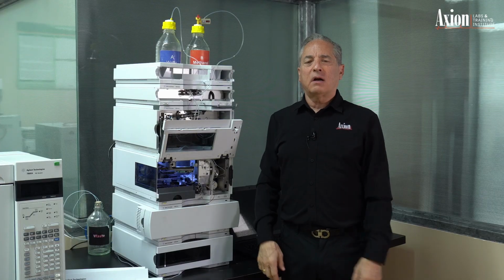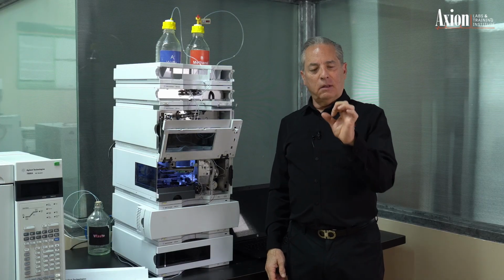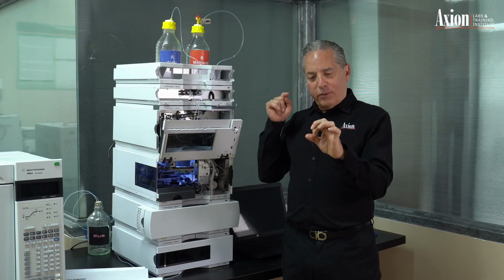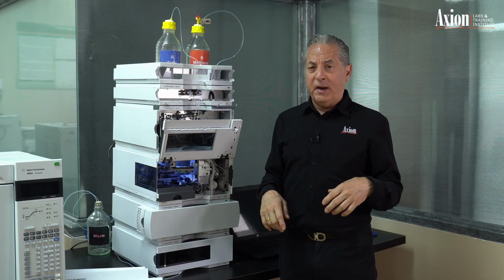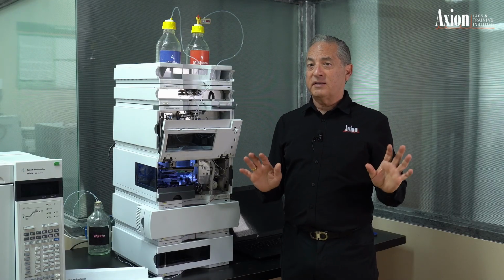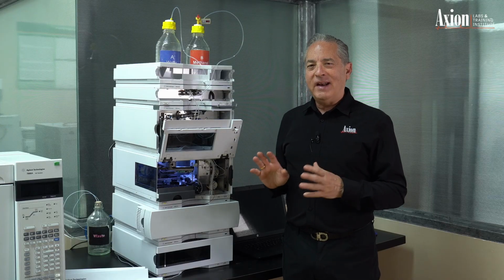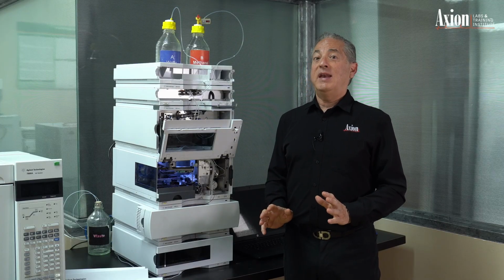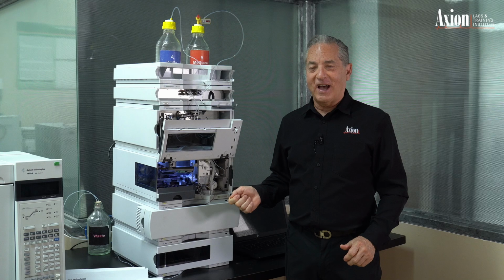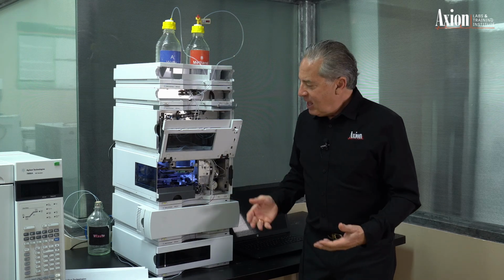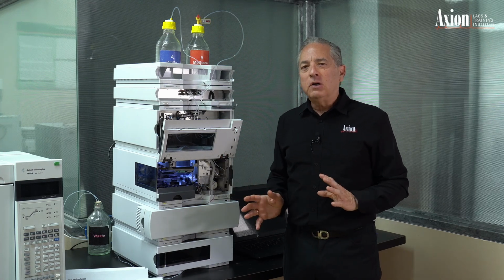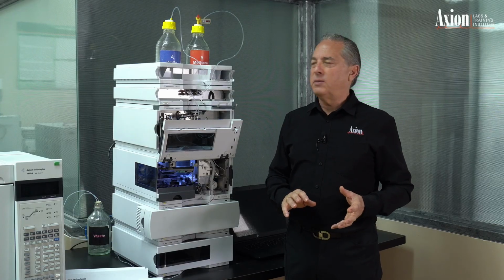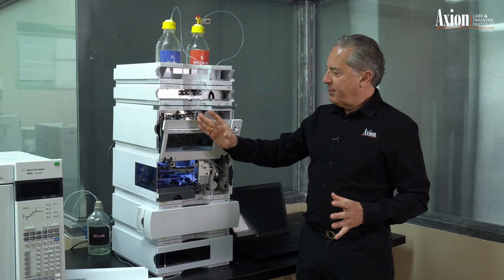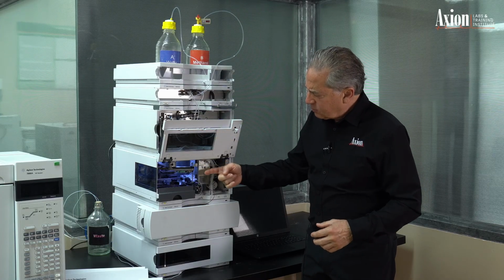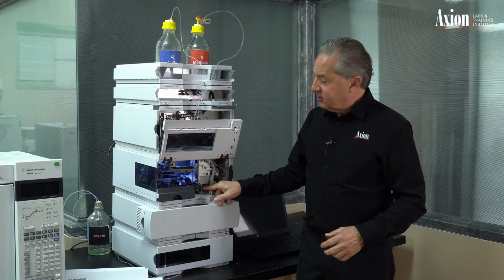Now in gas chromatography, it's simple. We have a little rubber septum, and we can stick a needle through the rubber septum because the GC is operating at 10 or 20 or 30 or maybe 50 psi. We're now operating at 9,000 psi. We cannot stick a needle into that 9,000 psi because we couldn't hold back the plunger. So we need to isolate the high pressure and the low pressure part of the instrument. So I got high pressure flow coming from the pump, coming through this piece of tubing. It enters the injection valve.